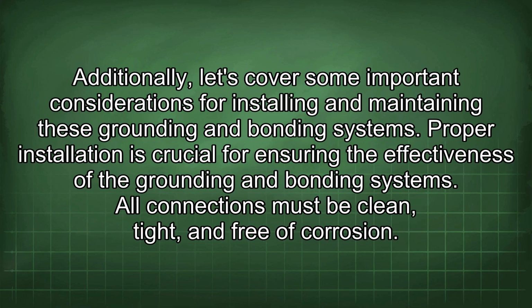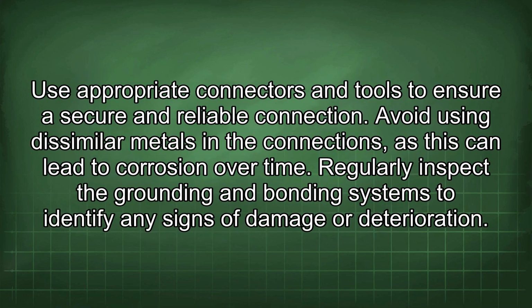Additionally, let's cover some important considerations for installing and maintaining these grounding and bonding systems. Proper installation is crucial for ensuring the effectiveness of the grounding and bonding systems. All connections must be clean, tight, and free of corrosion. Use appropriate connectors and tools to ensure secure and reliable connections. Avoid using dissimilar metals in the connections, as this can lead to corrosion over time.